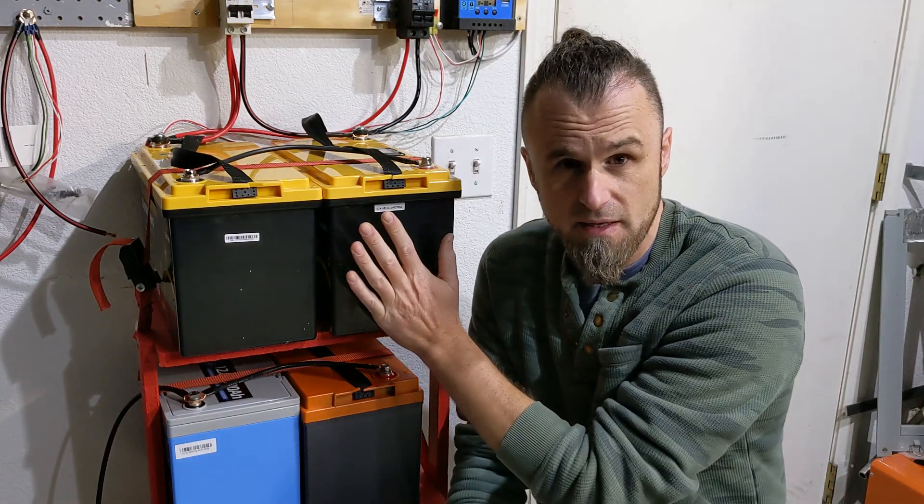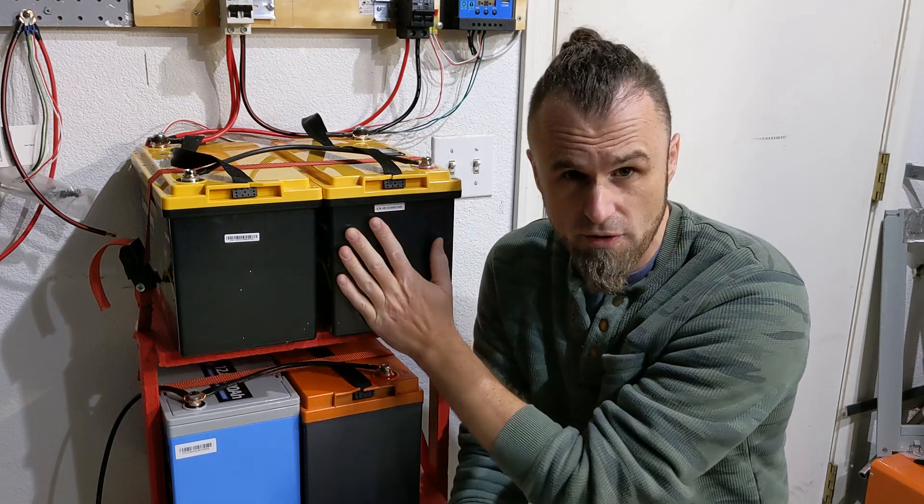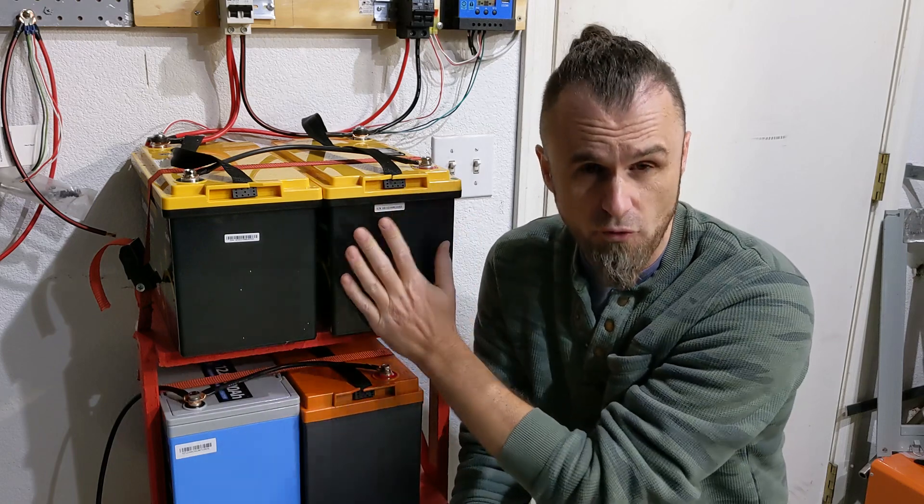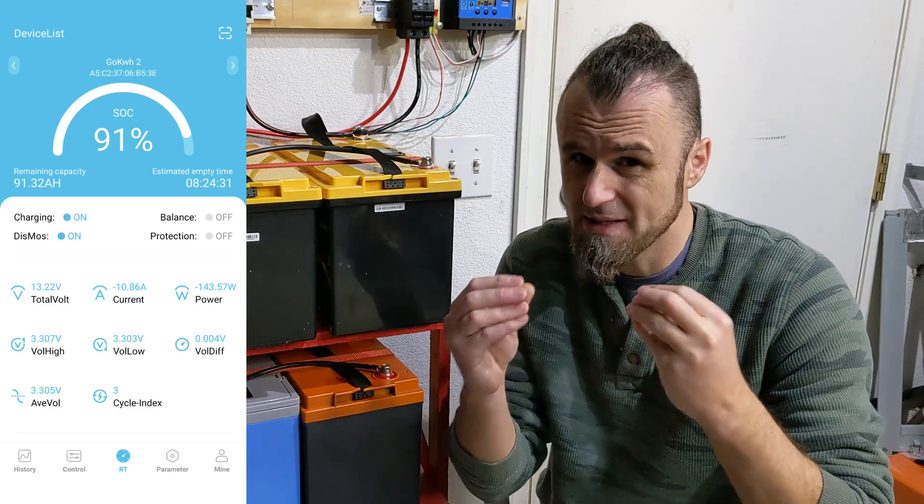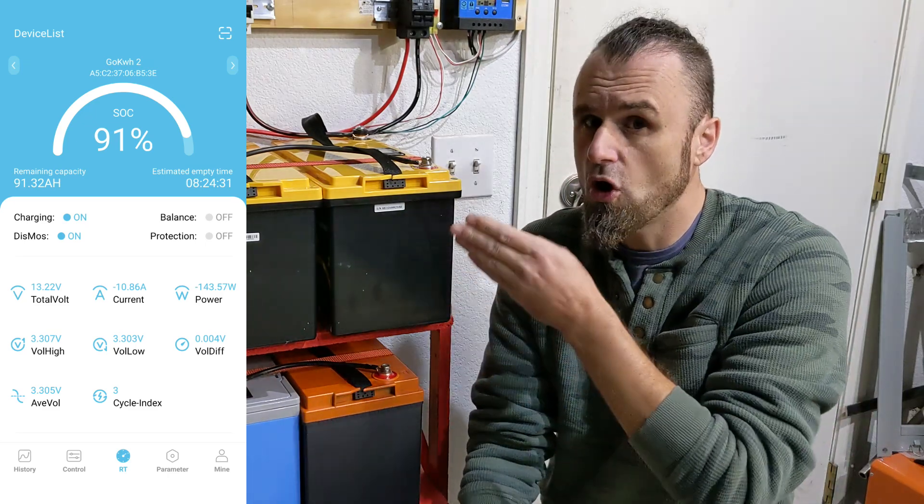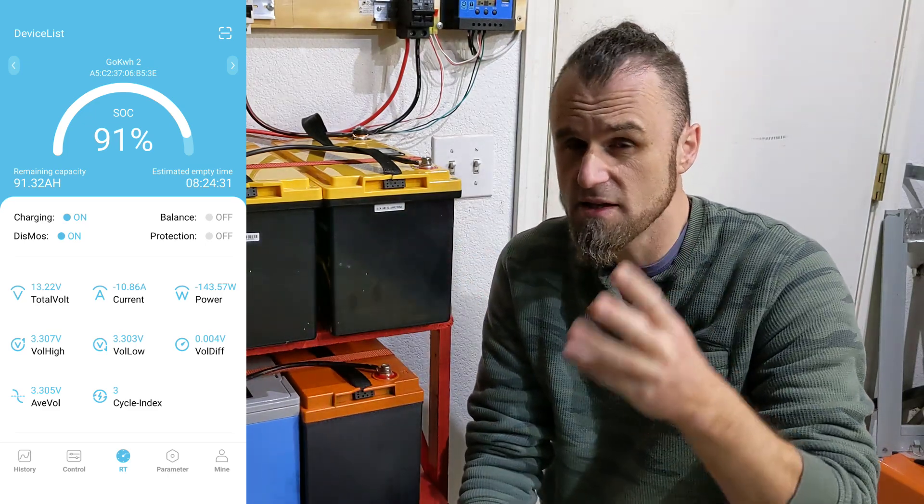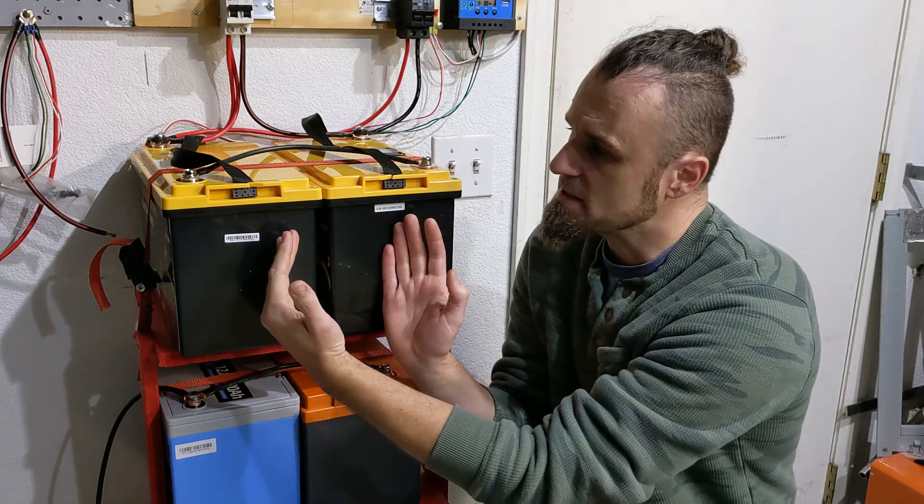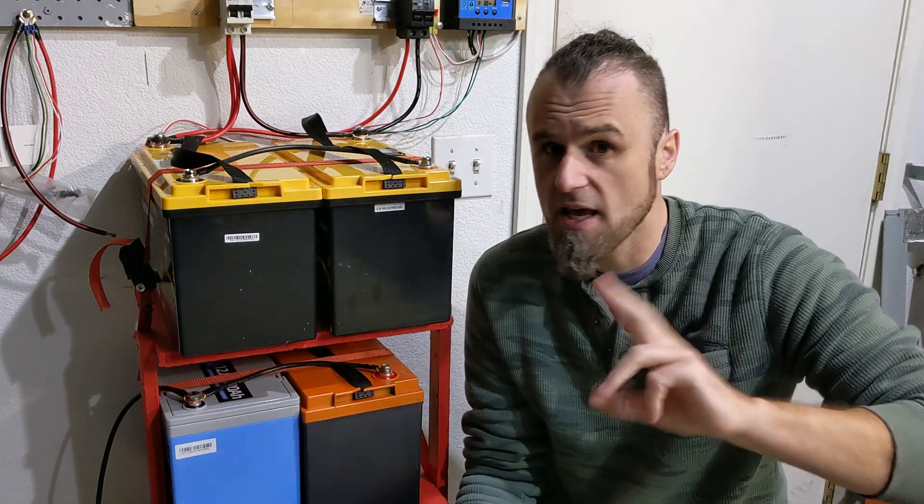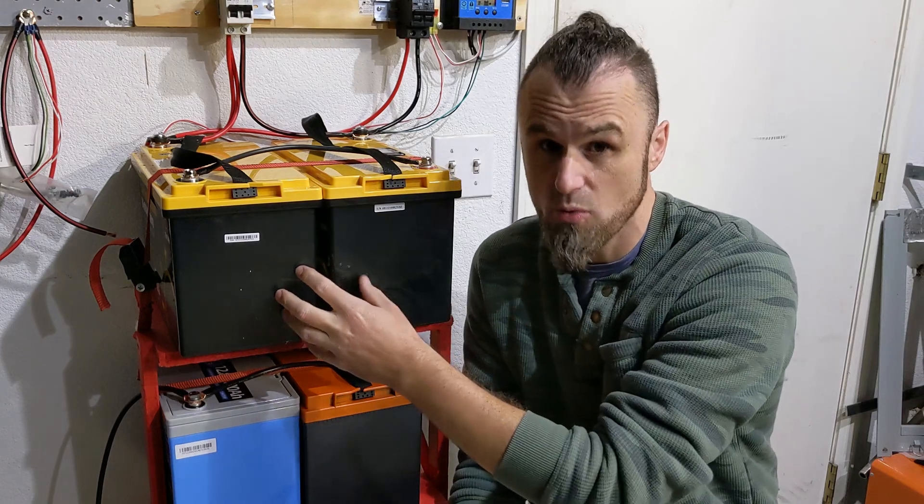These batteries are made in 12 volt, 24 volt, 36 volt, 48 volt, and they have a BMS - a battery management system that can control all the cells. This one has four cells in it, each one is like three volts, that's why it makes it 12 volt. If you hook them up in series, most of the BMSs cannot talk to each other, even from the same brand.